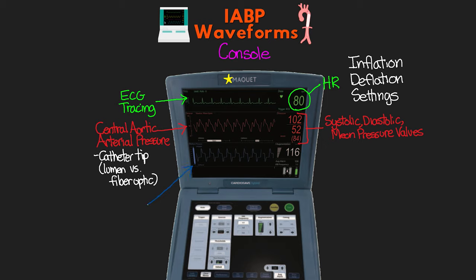Below the arterial pressure waveform, in blue, you're going to see the balloon pressure waveform. On the far left, you'll see a little animation of the balloon inflating and deflating. To the right of the waveform, you'll see the augmentation pressure displayed in white — this is something I'll discuss more in a minute. I will come back to this screen throughout this lesson and the remaining lessons in the series.